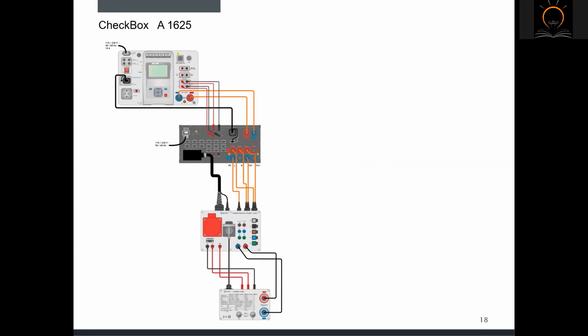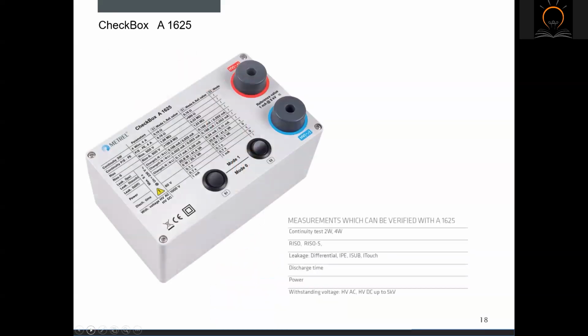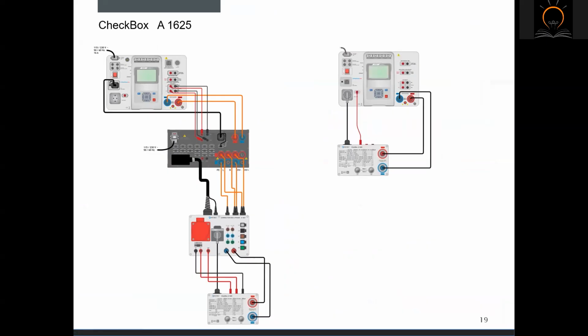A1625 checkbox contains built-in electronic component with reference values to confirm the measuring system operates correctly. It can be used for testing correct functionality of the test system and all standard equipment. The A1625 offers checking for the following instrument functions: continuity of protective bonding, insulation resistance, leakage currents, power measurement, residual voltage or so-called discharging time, and withstanding test, or let's say HV HIPOT test. To verify the complete system, the following connection must be executed.